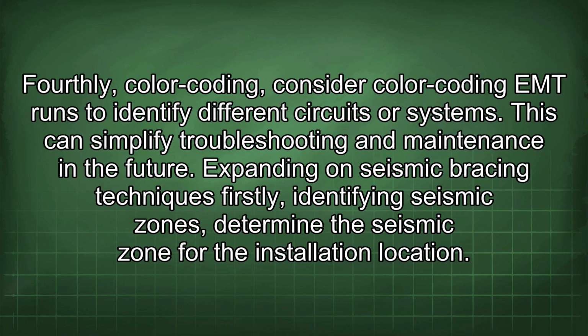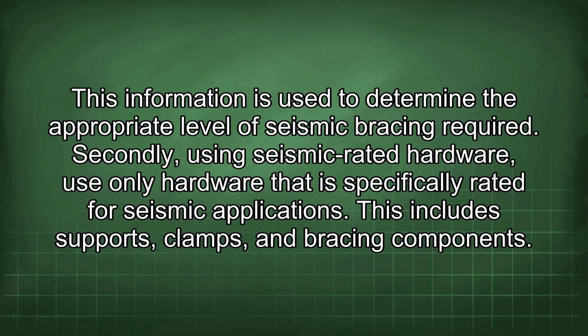Expanding on seismic bracing techniques. Firstly, identifying seismic zones. Determine the seismic zone for the installation location. This information is used to determine the appropriate level of seismic bracing required. Secondly, using seismic rated hardware. Use only hardware that is specifically rated for seismic applications. This includes supports, clamps, and bracing components.